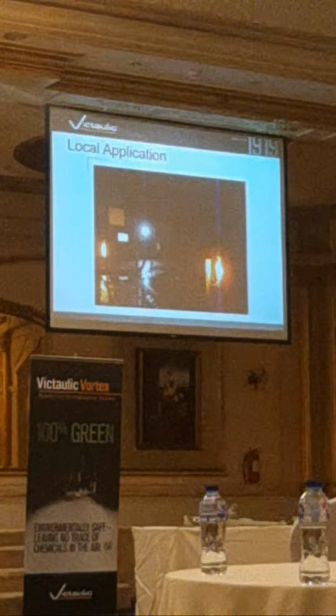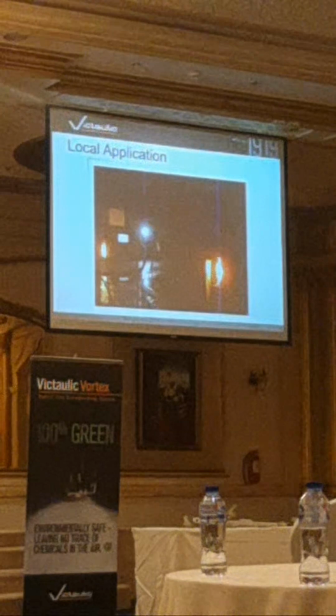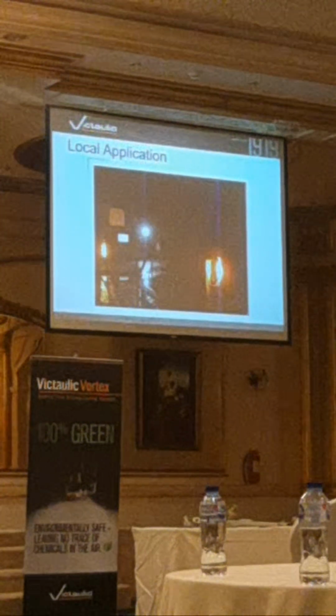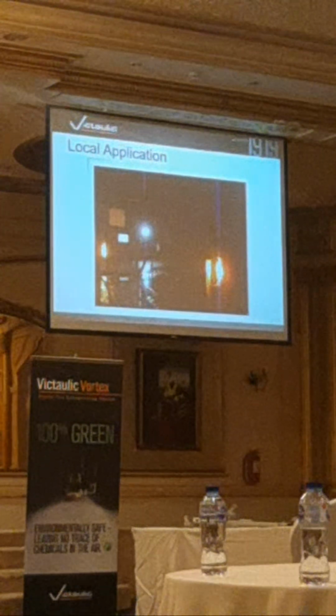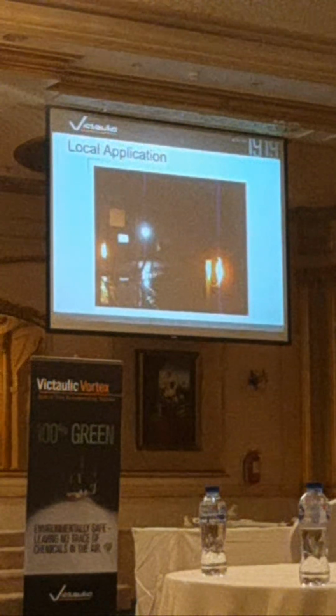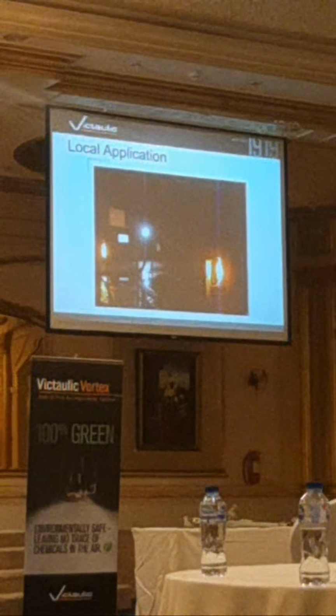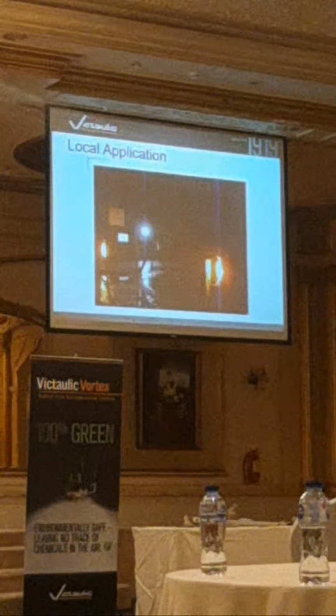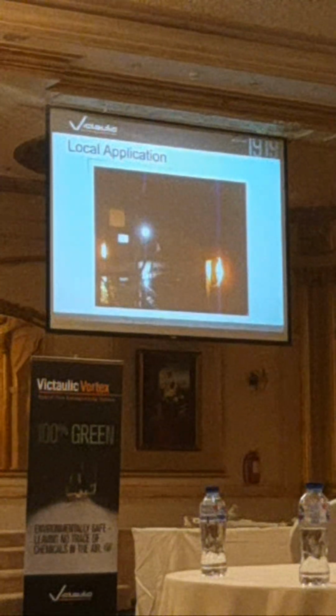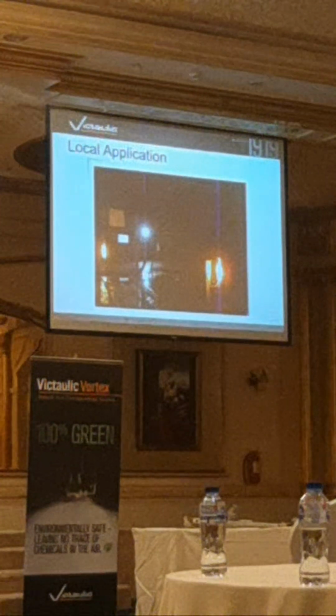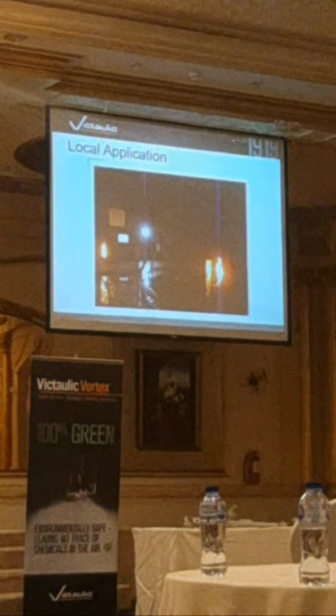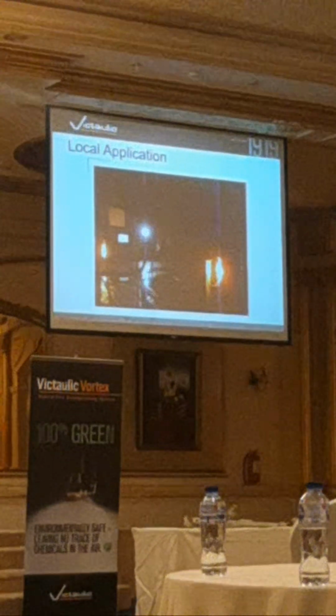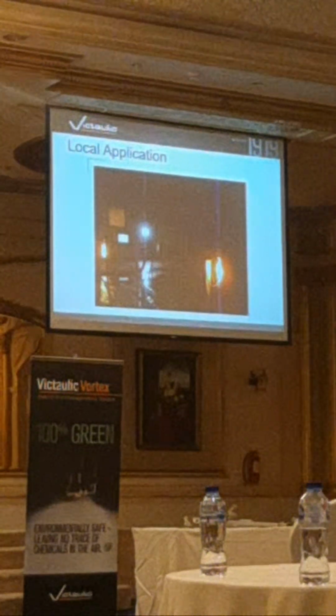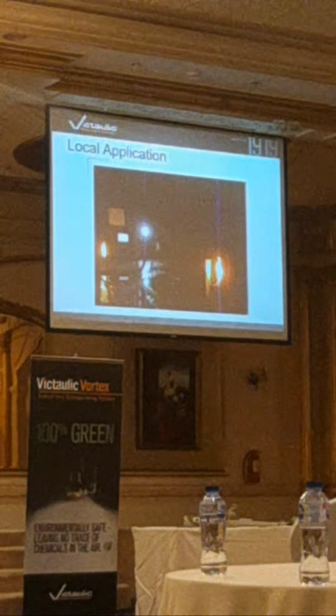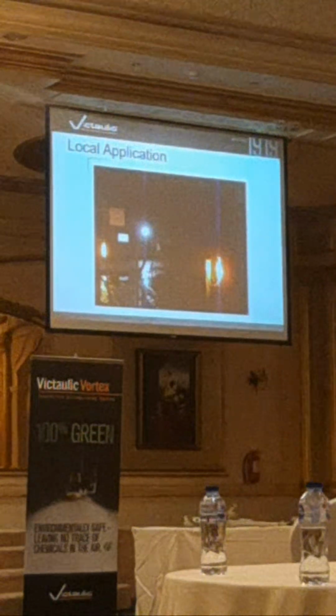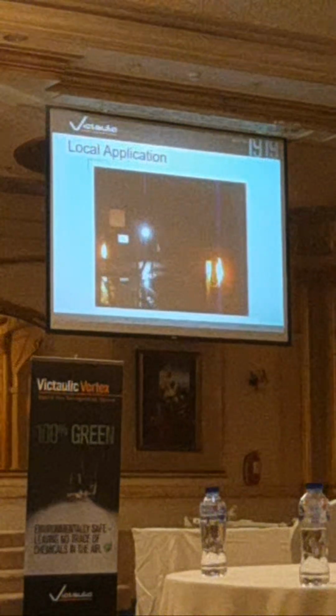On top of that, you might see it a little bit in the shadow, a diesel spray. At a certain point during the activation, diesel will be actively spraying on top of the live fire. What is this simulating? A generator, a turbine, any sort of machine with a broken fuel connection. The fuel is gathering on the floor, and you don't have an ignition yet. There's not yet a fire, but there's active fuel just spraying under pressure. At a certain point you might have an ignition, and everything goes, and on top of that you're just spraying additional fuel on it.